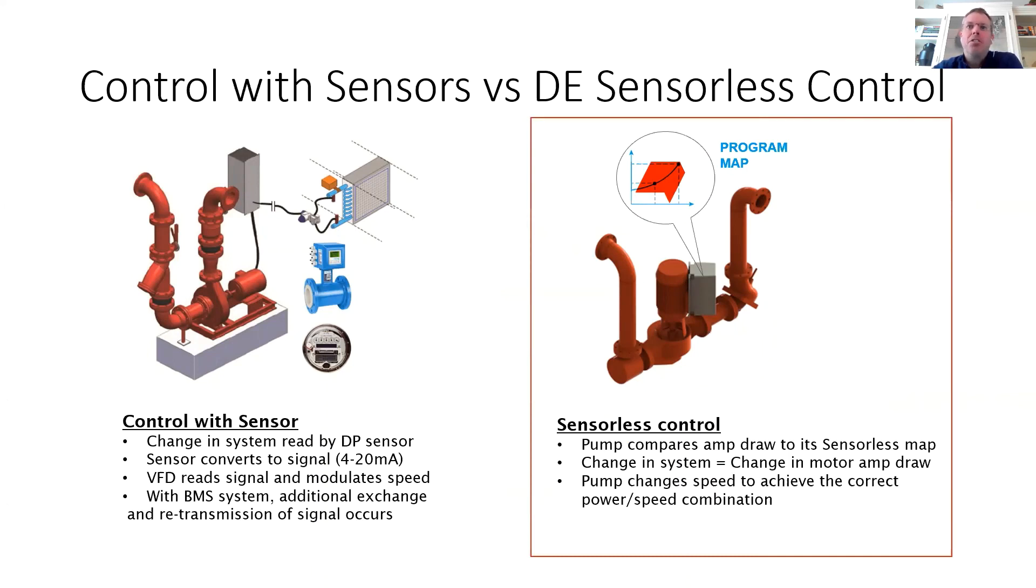In comparison, design envelope sensorless control monitors pump speed and motor amp draw, compares it to its sensorless map and control curves, and as changes occur out in the system, the pump speed changes to achieve the correct power and speed combination. So the BMS system, through one BACnet connection, can pull in power consumption, pump speed, pump flow, pump head, status, and alarms, which can eliminate as many as four separately installed devices and takes out the guesswork as to where to install a DP sensor.